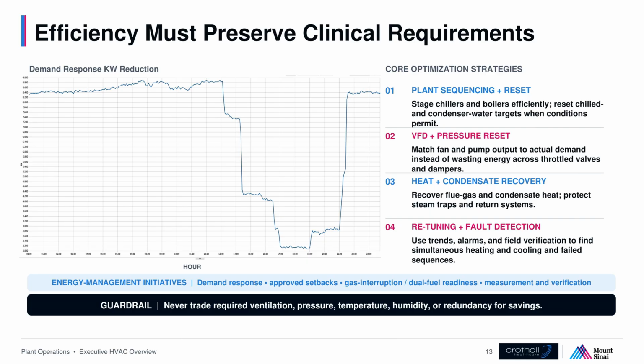Every reset must protect coil dehumidification, minimum airflow, room pressure, and equipment limits. VFDs let pumps and fans match output to demand, while plant sequencing prevents extra chillers, boilers, pumps, or tower cells from running unnecessarily. Demand response reduces peak kilowatts during a grid event. Energy efficiency projects reduce kilowatt hours every day. Utility incentives can offset qualifying project costs, but savings must be commissioned and measured. BAS retuning, heat and condensate recovery, reliable steam traps, and field verification complete the strategy. During a natural gas interruption, the boiler plant transfers to fuel oil before the interruption begins. The guardrail remains absolute. Never trade required clinical conditions, redundancy, or continuity for savings.